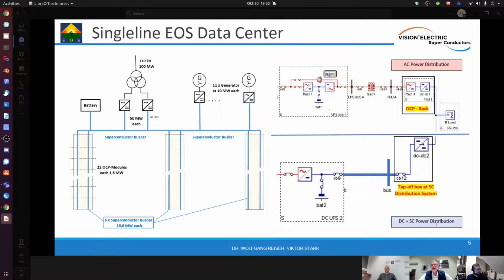Yeah, you see it directly: there are more components in the AC power distribution than in the DC and superconducting power distribution. Starting at the battery rectifier and the battery itself: on the upper part you have your rectifier feeding the battery, and a converter converting the DC voltage back to AC, because you want to transport a lot of high energy at a higher voltage level to reduce losses. This is the only possibility with conventional material—reducing losses by increasing voltage and reducing current. Such a transformation with a transformer is only possible with AC, so you need a lot of components to reduce power losses.